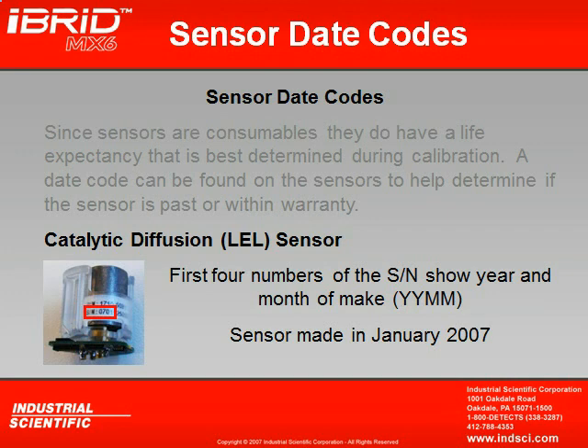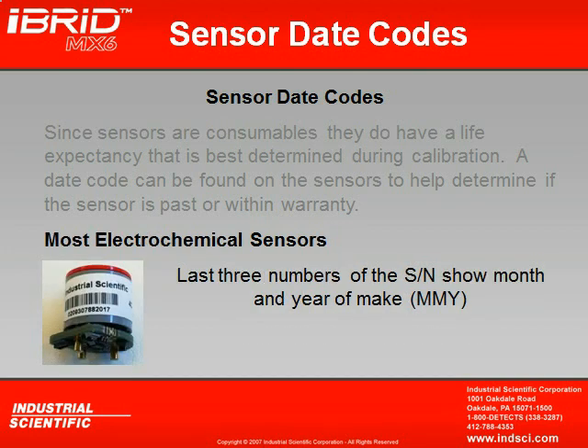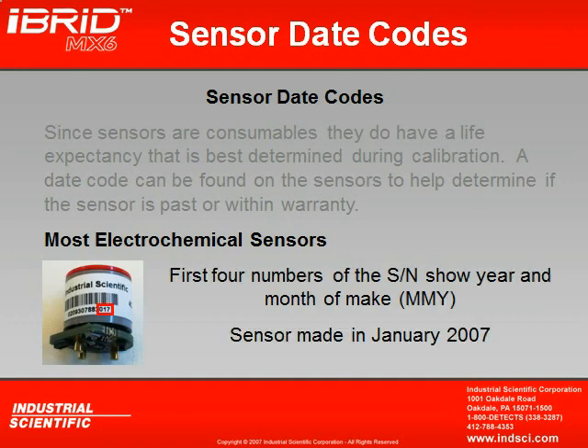Now, electrochemical sensors are a little bit different. To read the date code of your electrochemical sensors, we're now going to use the last three numbers of the serial number, and it goes month and year of make. So looking at the last three numbers here, we see 017. That would indicate first month, January. 7 would indicate 2007 when the sensor was made.